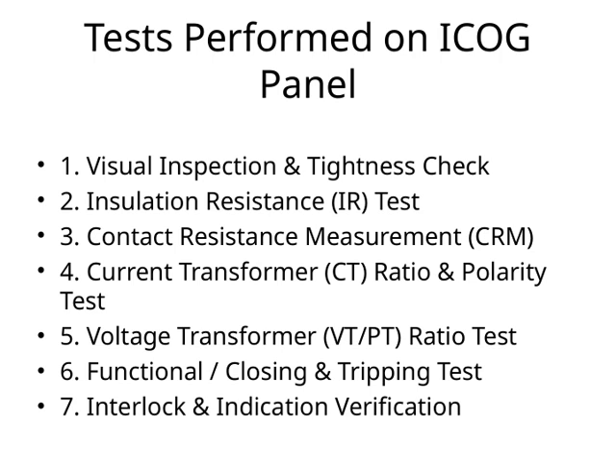Next, we have the insulation resistance, or IR, test. This test helps us ensure that the insulation within the panel is intact and effective, preventing any unwanted current leaks that could cause faults or safety hazards. Then there's the contact resistance measurement, or CRM. This measurement is important because it assesses the quality of electrical contacts within the panel, ensuring low resistance for efficient power flow and reliable operation.